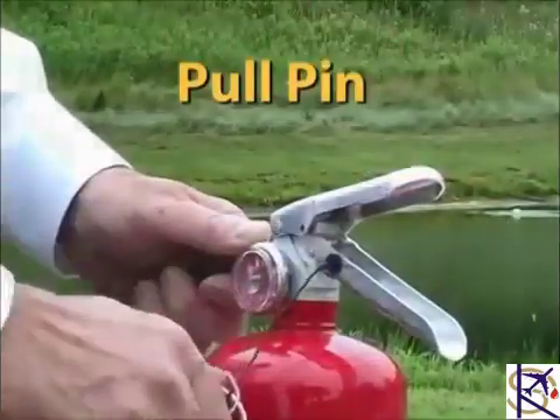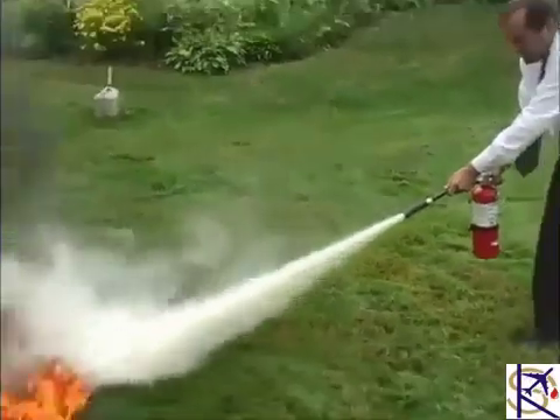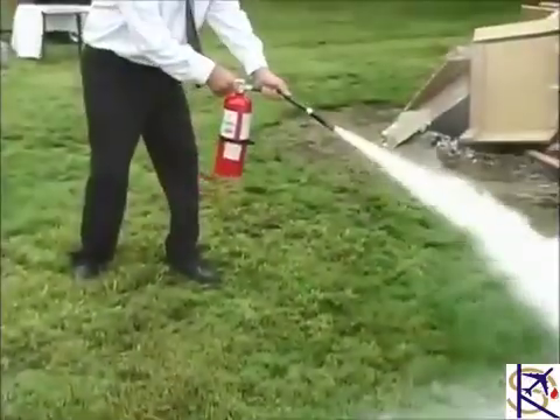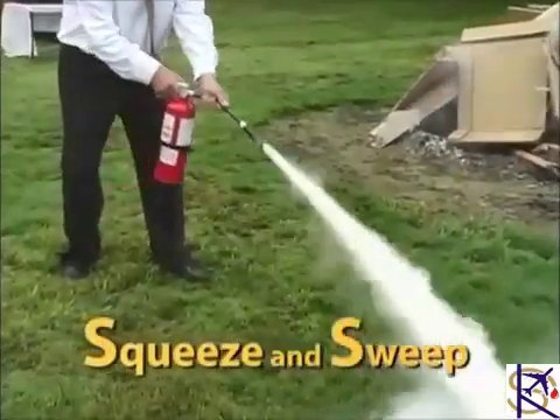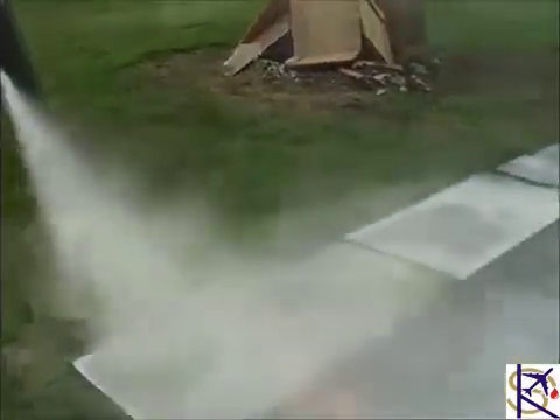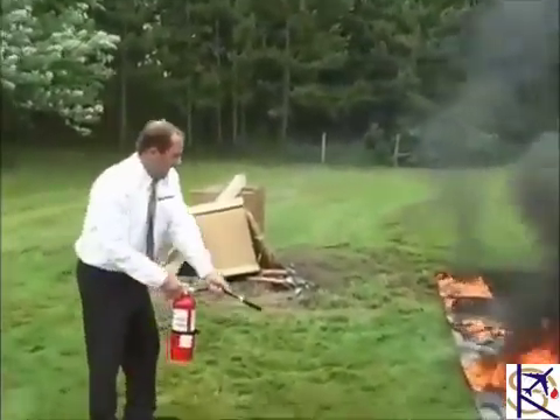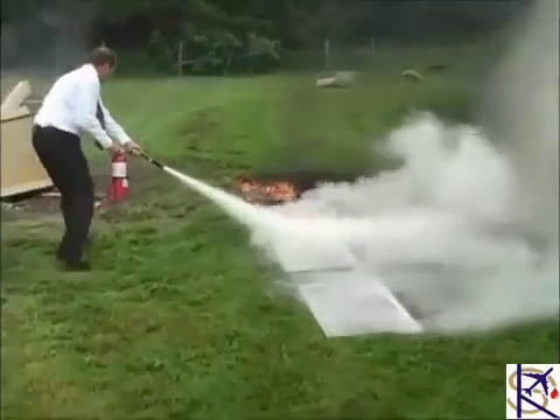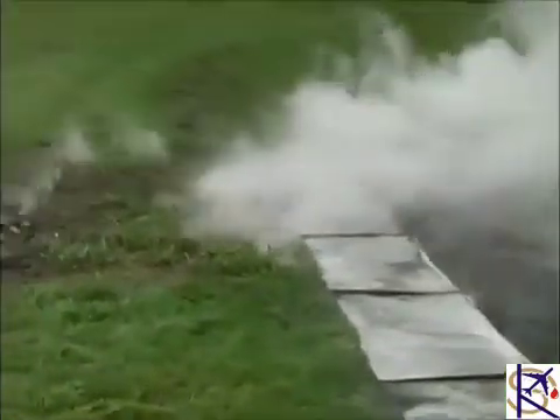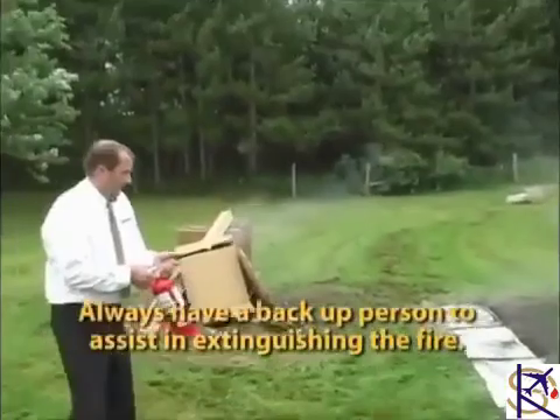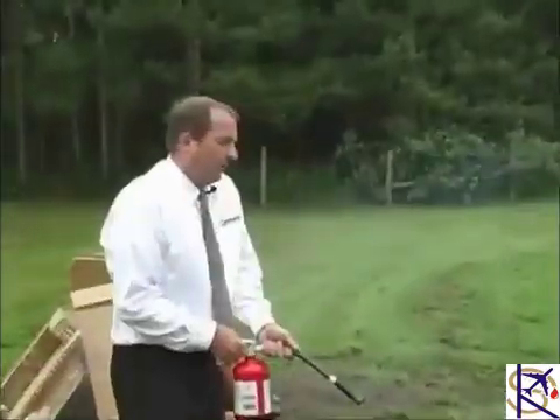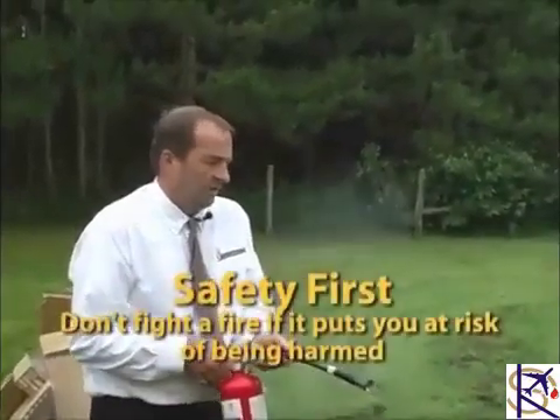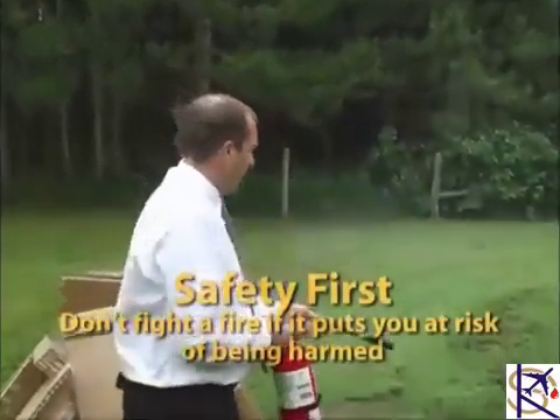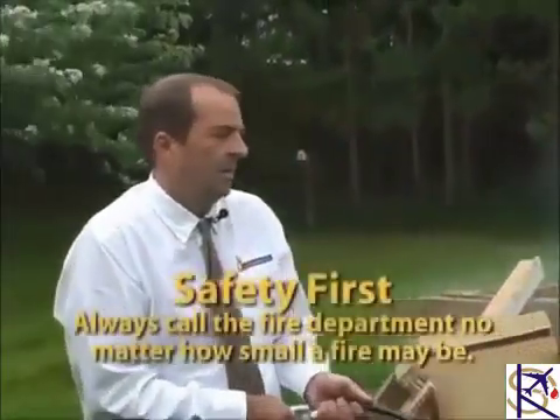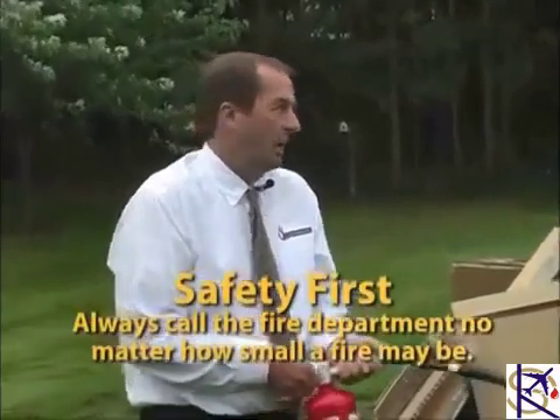Pull the pin, aim at the base of the fire, sweeping motion. I'm using a 5-pound ABC, aiming at the base of the fire. Slow sweeping motion. You should always have a backup person just in case you're overcome. And the important thing is don't fight the fire unless you're safe trying to put it out. Don't put yourself at risk. Wait until the fire department comes for them to do their job.